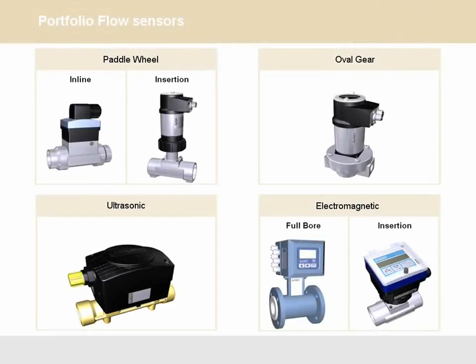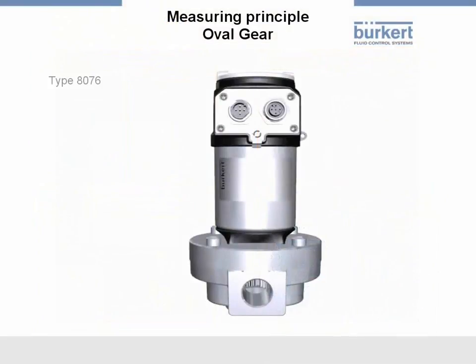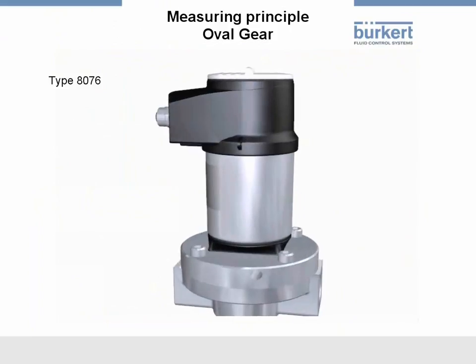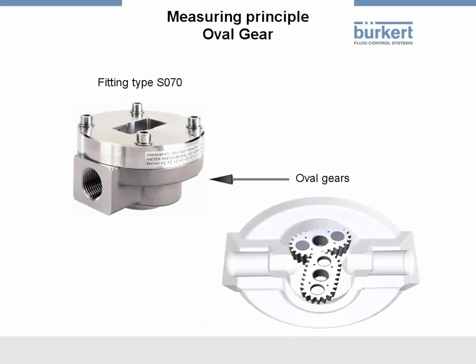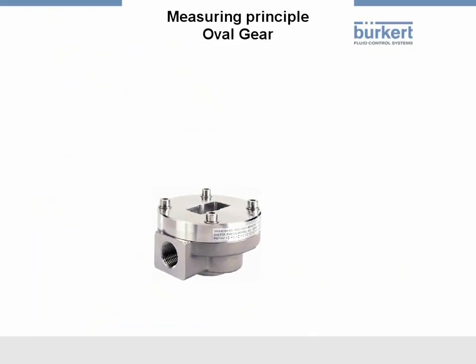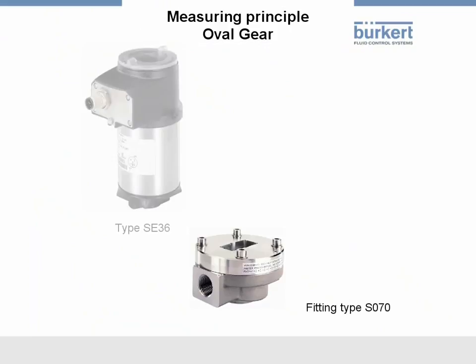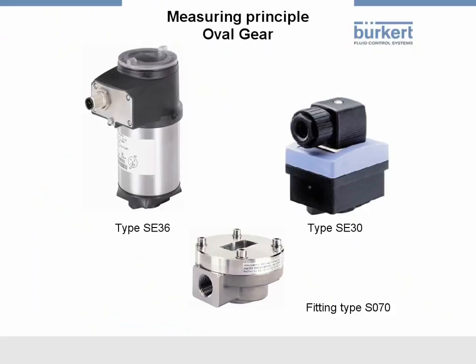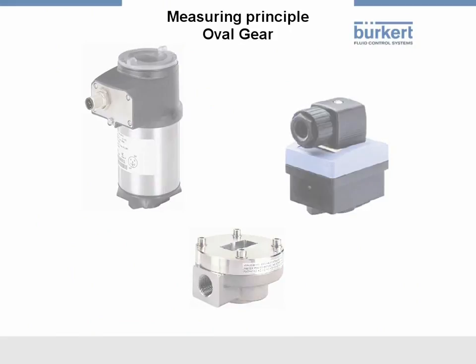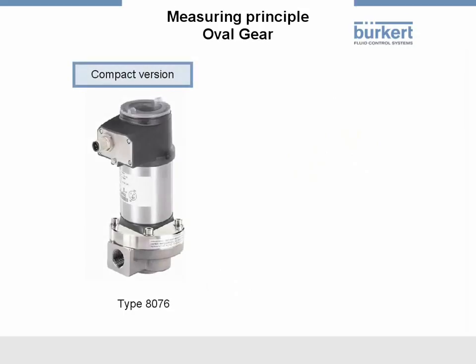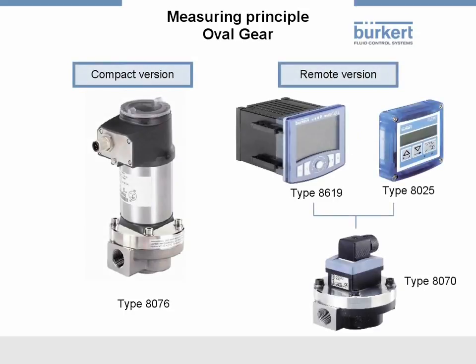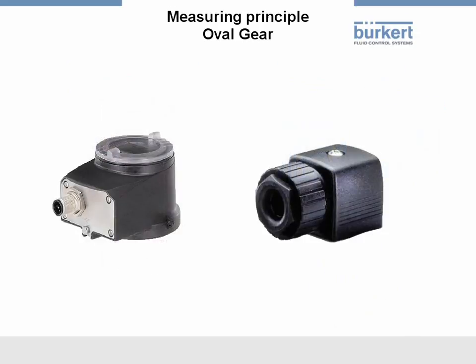Now that you've learned quite a bit about flow measurement with a paddle wheel, we'll now examine flow measurement with oval gears. How are these devices designed? Flow meters with oval gears use an inline fitting where the oval gears are located. An electronic circuit with or without a display is mounted on the fitting. As an alternative to this compact unit, a version with remote electronics is also available. The electrical connection is implemented with an M12 connector or a cable gland.